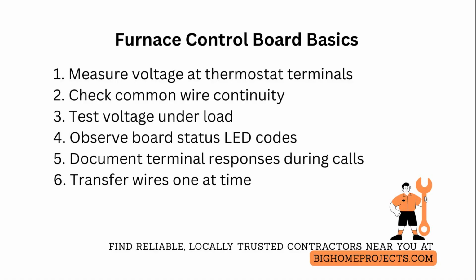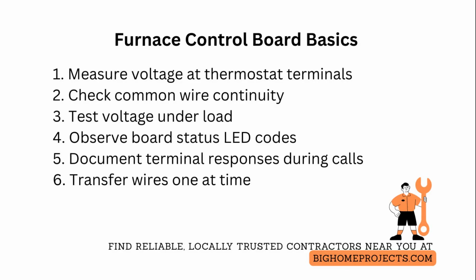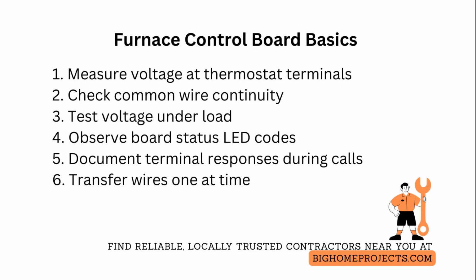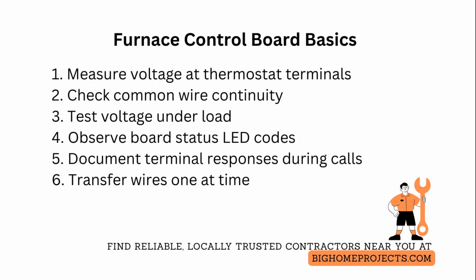When you replace the board, transfer one wire at a time and label both ends, confirming fan center tap and blower speed taps are matched to the original harness to prevent overcurrent on the motor. If the furnace had intermittent lockouts, enable the board's diagnostic logging if available or monitor flame sense current. Low microamp readings mean a dirty electrode or weak ground return.